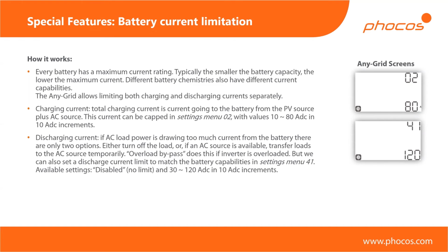Typically, if you have a battery management system inside, the BMS will simply notice that there's too much current going into the battery and will shut down. So basically your battery will just turn off if it's well protected, or it could even be damaged if it's not well protected. So this is an important setting if you're using small batteries. You can limit the charging current that's going into the battery.